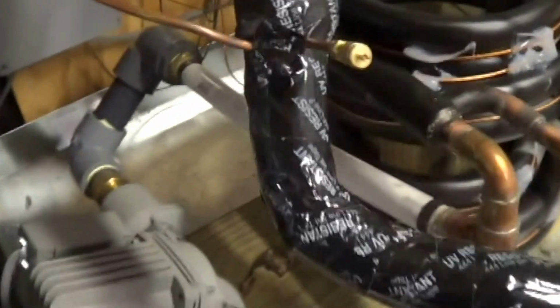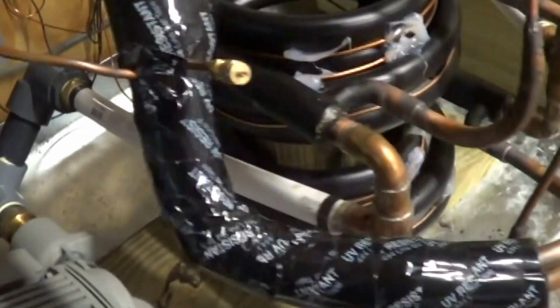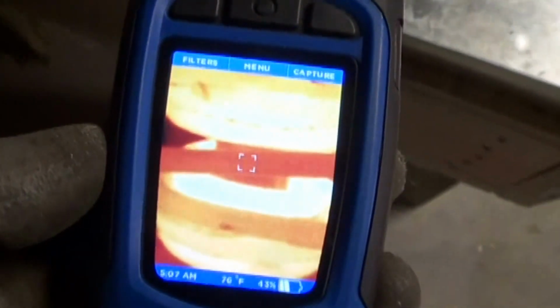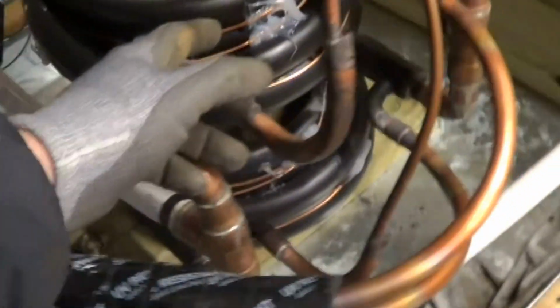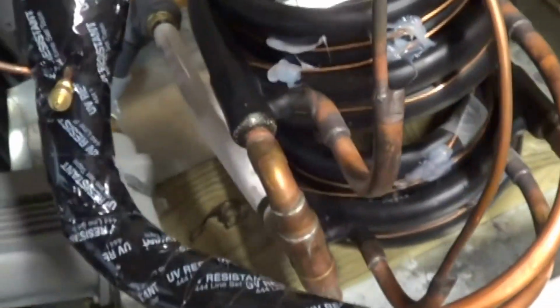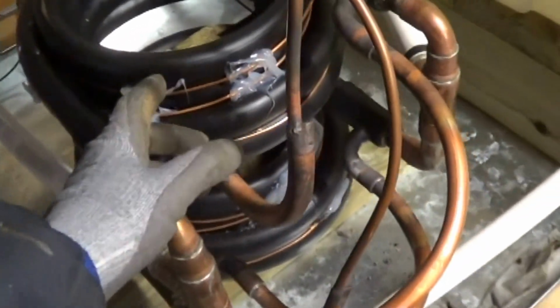I got some performance data here because I've been tweaking it a little bit. So since the water's warmed up, you see how the 7 tons worth of coil, they're fully being utilized. The last row is where we're getting our subcooling and running about 15 degree subcooling. There's the outlet for the liquid. So all of the coils are being utilized because the water's warmed up.